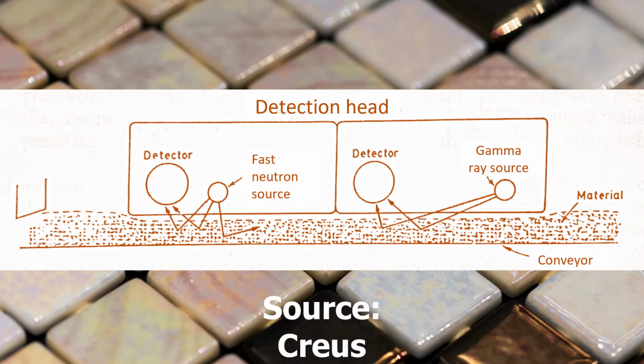In the radiation method, a high-energy neutron source is directed against the processed material, and part of the emitted radiation is reflected mainly by the hydrogen atoms existing in the material's molecules. Since hydrogen is chemically associated with water, it is possible to determine the moisture of the material very accurately. The method is expensive, requires safety monitoring, and periodic checking of the neutron source.